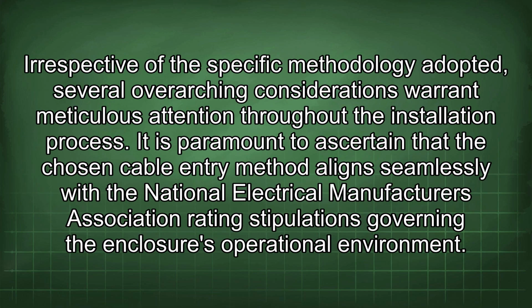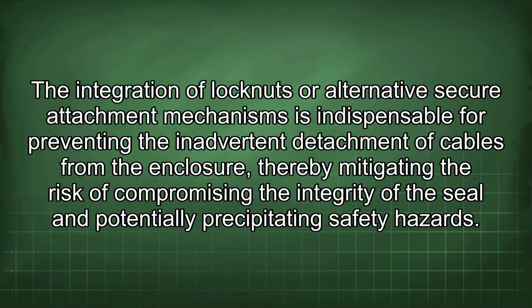Irrespective of the specific methodology adopted, several overarching considerations warrant meticulous attention throughout the installation process. It is paramount to ascertain that the chosen cable entry method aligns seamlessly with the National Electrical Manufacturers Association rating stipulations governing the enclosure's operational environment. The integration of lock nuts or alternative secure attachment mechanisms is indispensable for preventing the inadvertent detachment of cables from the enclosure, thereby mitigating the risk of compromising the integrity of the seal and potentially precipitating safety hazards.